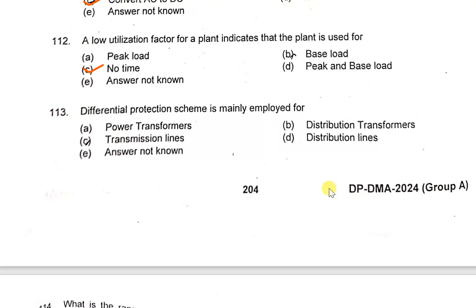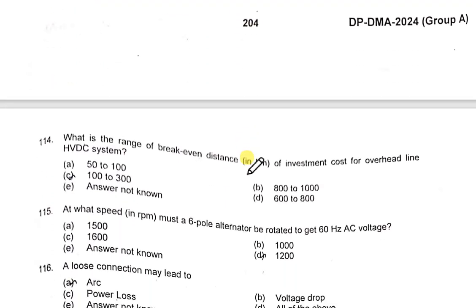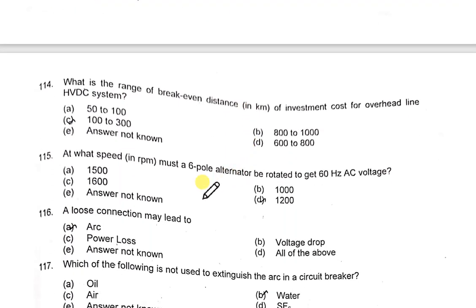Differential protection scheme is mainly employed for power transformers. For transmission lines, distance protection is used. The break-even distance for investment cost comparison between overhead line and HVDC system is around 600 to 800 km.